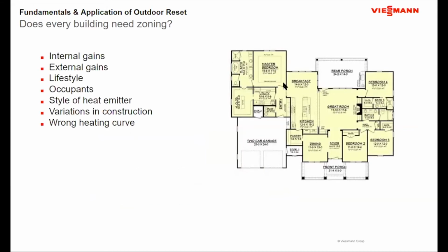Throughout the building, there's going to be internal and external gains on that building. Outdoor reset in and of itself without feedback isn't going to accommodate those. So there's going to have to be zoning to take care of those. It may be because of the lifestyle of the individual, so different rooms may want to be different temperatures. It may also be based on the occupants of the building.